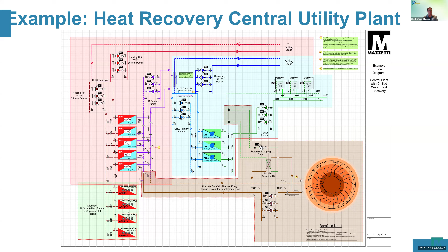ASHRAE has come up with Guideline 36, which is a set of canned control sequences. The intent is to simplify the design, the construction, and the commissioning. I'll get into an example shortly about why we need it. These are actual numbers they've come up with on a full retrofit site using these guidelines. They're getting these kinds of savings from MOBs and office buildings. Software-only retrofits are getting smaller but appreciable savings.